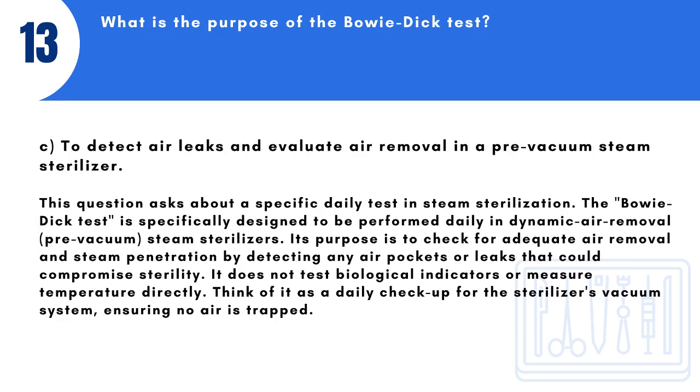Answer: C. To detect air leaks and evaluate air removal in a pre-vacuum steam sterilizer. This question asks about a specific daily test in steam sterilization. The Bowie-Dick test is specifically designed to be performed daily in dynamic air removal, pre-vacuum, steam sterilizers. Its purpose is to check for adequate air removal and steam penetration by detecting any air pockets or leaks that could compromise sterility.